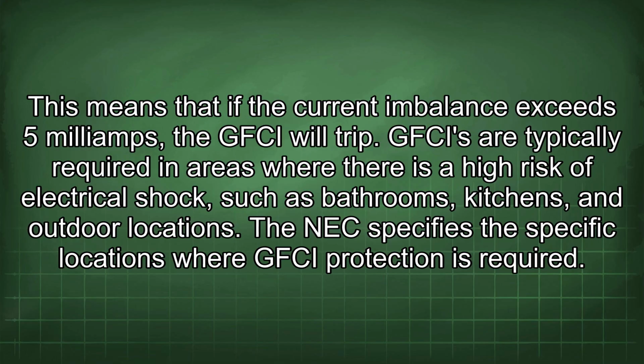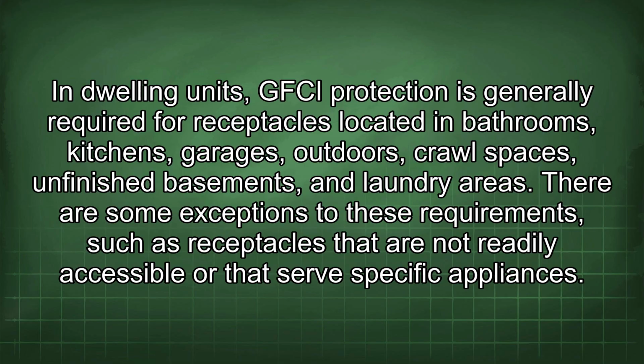GFCIs are typically required in areas where there is a high risk of electrical shock, such as bathrooms, kitchens, and outdoor locations. The NEC specifies the specific locations where GFCI protection is required. In dwelling units, GFCI protection is generally required for receptacles located in bathrooms, kitchens, garages, outdoors, crawl spaces, unfinished basements, and laundry areas. There are some exceptions to these requirements, such as receptacles that are not readily accessible or that serve specific appliances.